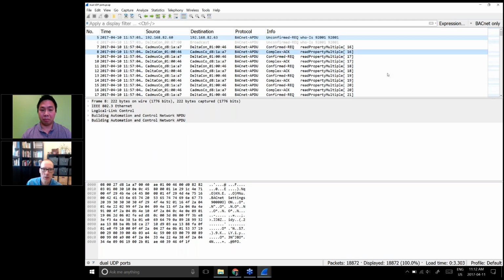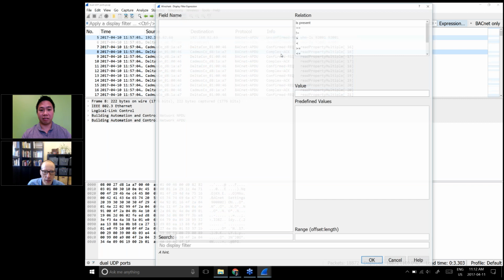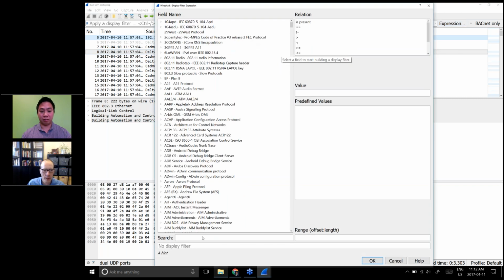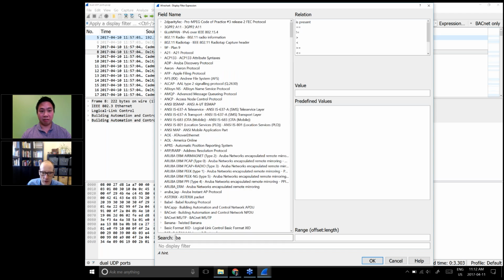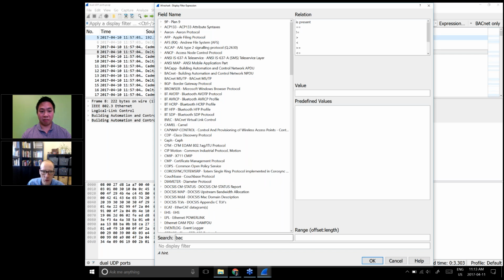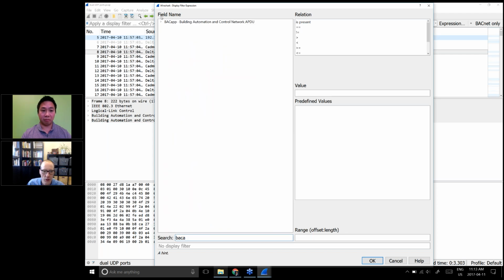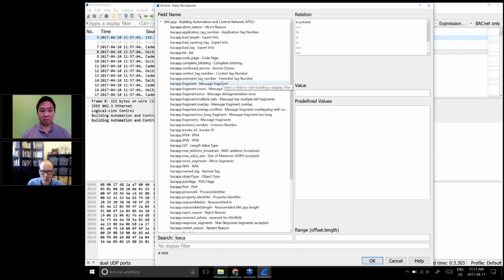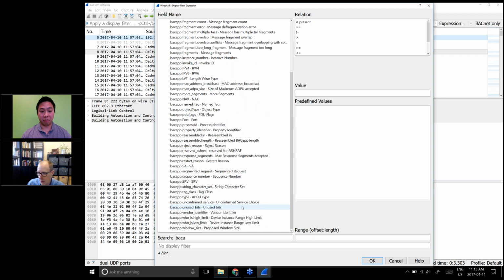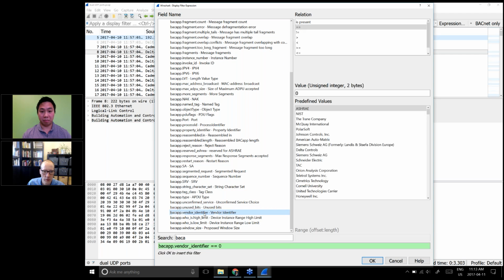The one thing I will point out though is, hey, Ping, can you click on the expression button at the end of the line there? Absolutely. Yeah, so the thing about it is, how did Ping know what to type? He typed that in there because he's done it a million times, but how did he know that? Well, if you hit expression, you get a big long column list of every protocol Wireshark knows. And if you look at, yeah, you can see how he's searching. If you look under BACapp, you will find all the little sub-elements of a BACnet protocol application. So this is APDU components. So Ping was clicking on unconfirmed service there.